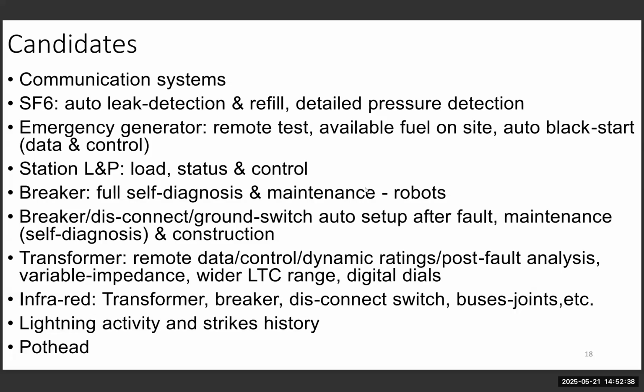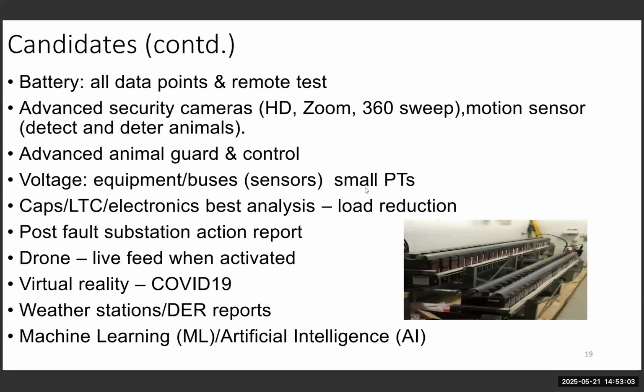Pothead—POT stands for point of termination. Anytime you transition, let's say from overhead to underground, underground to overhead, or GIS to AIS, anytime the medium changes, you have this device. Historically this device has not been the most reliable—they do fail a lot. So a lot of utilities have invested in making them more reliable.